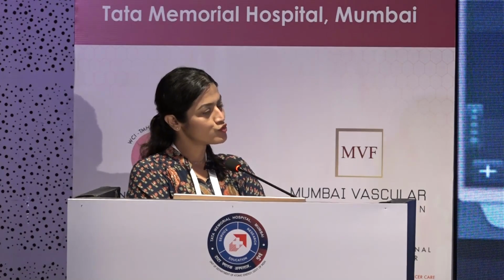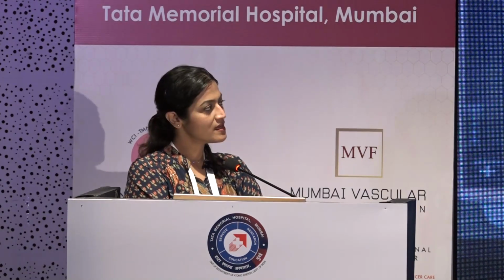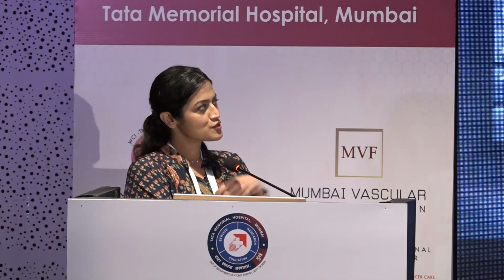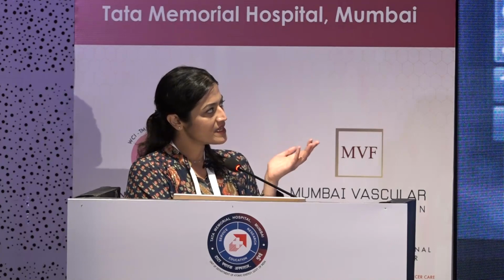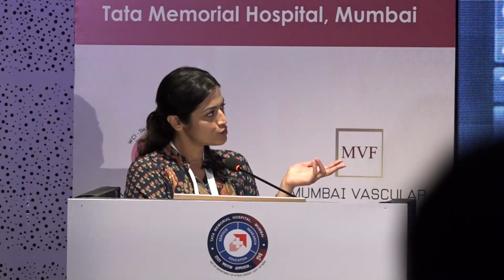So the acquisition time for each projection is about 35 to 45 seconds. If you do 3 standard acquisitions for a breast, it's going to be about 2.5 to 3 minutes for each breast. As you've seen, for the first 2 acquisitions, the frontal as well as the lateral one, you didn't have to change the patient position. In the same patient position, you could do 2 acquisitions, and depending on the breast size, for the medial breast, you may want to then remove the lateral wedge and make the breast fall straighter on the chest wall.